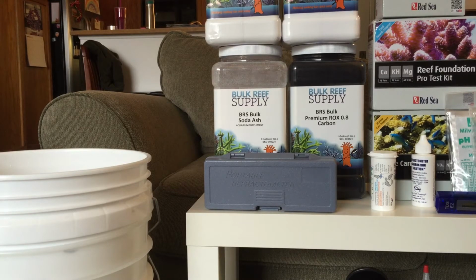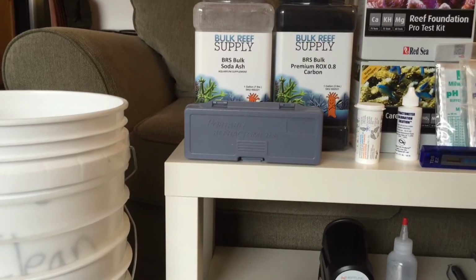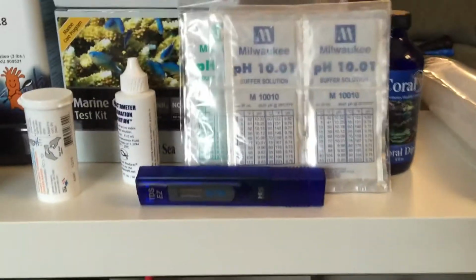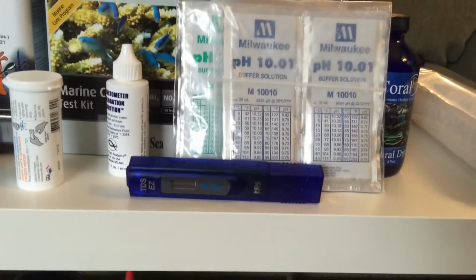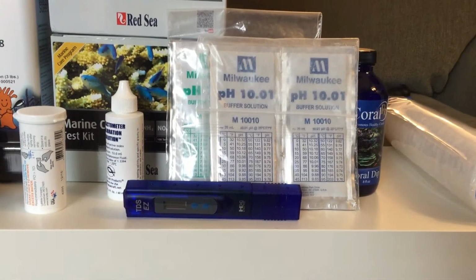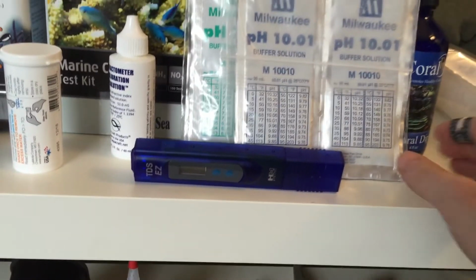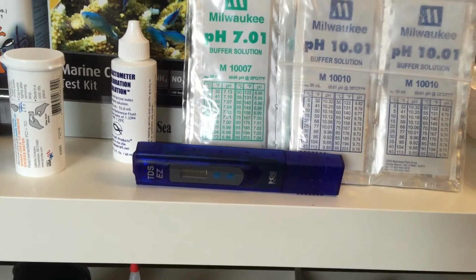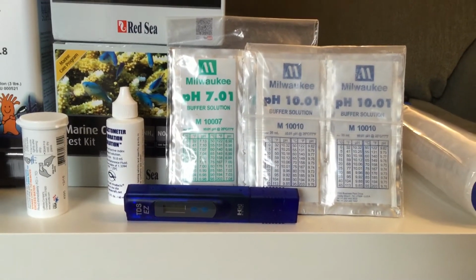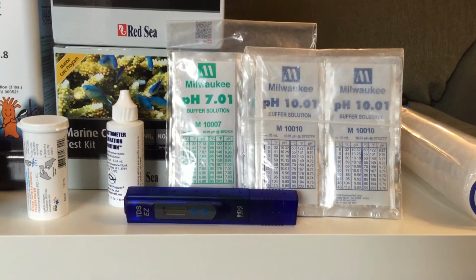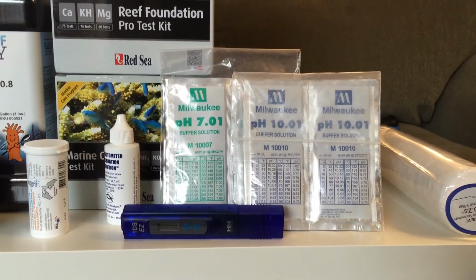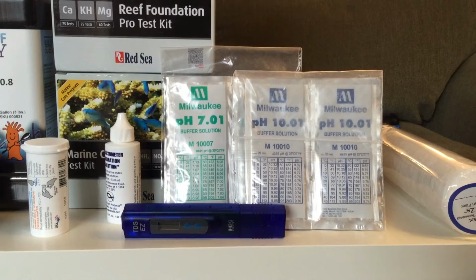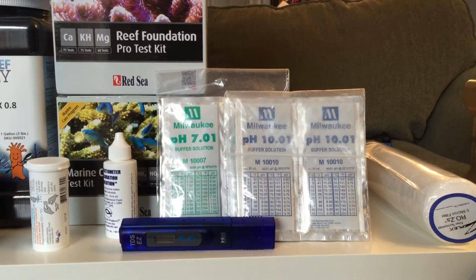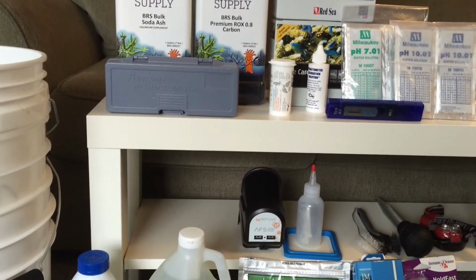Clean and recalibrate your probes. For cleaning your probes, you take this, and here I have the calibration solution. It's a really good habit—you probably don't have to do it every month, but it's best case scenario. It's really cheap: each of these packs has your pH 10 and pH 7, and whatever controller you have will explain exactly how to calibrate them. It's good to calibrate just to make sure your probe's not falling off too much. Once you start noticing your probe not keeping its calibration, it's time to replace it, probably once a year, or once every 2 years at most.